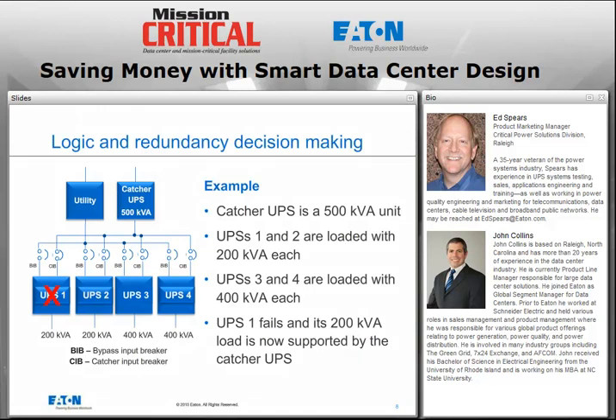So I'm going to spend a few moments describing the drawing at the left of this slide, and hopefully you can see my cursor as we do this. In this case, we show a system where I have a catcher UPS that's rated at 500 kVA, and its output feeds breakers called CIB that are feeding the bypass input of each of the 4 primary UPSs.